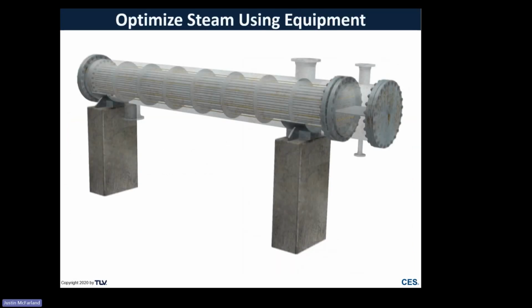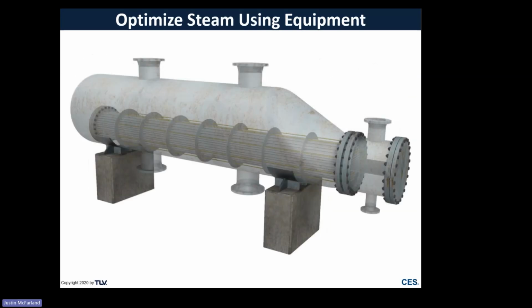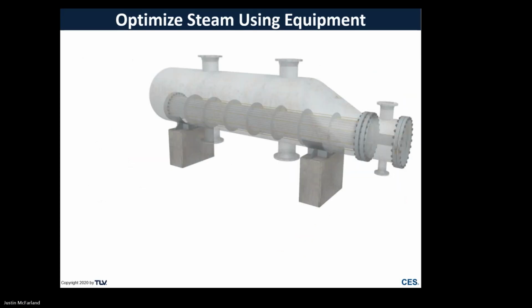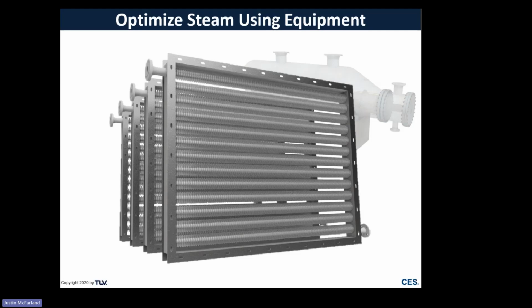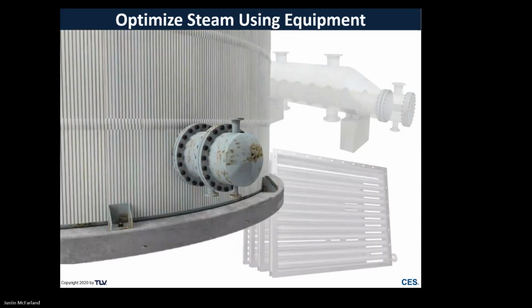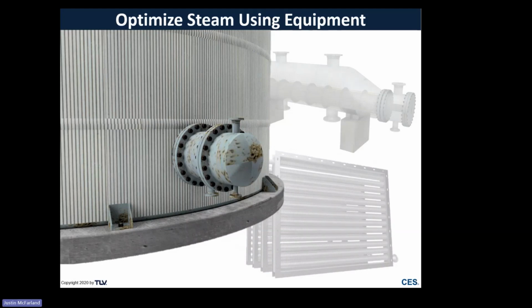So shell and tube heat exchanger. This is a typical shell and tube heat exchanger I'd see in heavy industry. Sometimes it looks more like a kettle type reboiler like this. There's lots of other different types of process heating steam heat exchangers, whether it's things like a fin tube heater for combustion air, or for HVAC for an air duct for comfort heating. Or something like a tank heater, plate and frame, U-tube, lots and lots of different types of configurations.